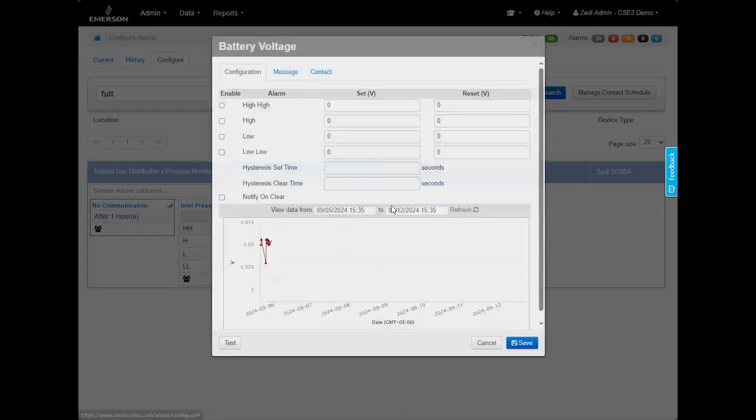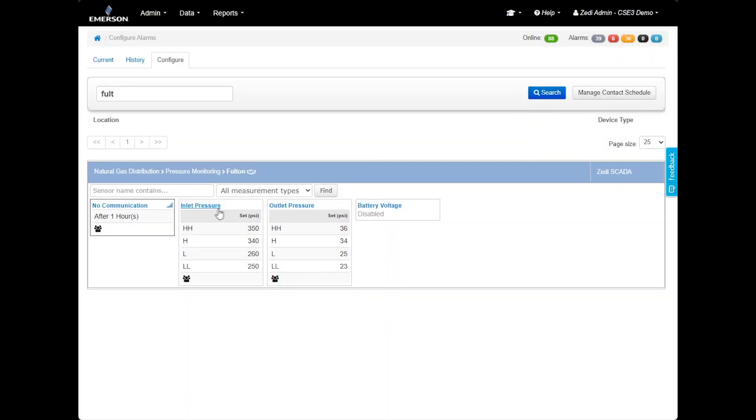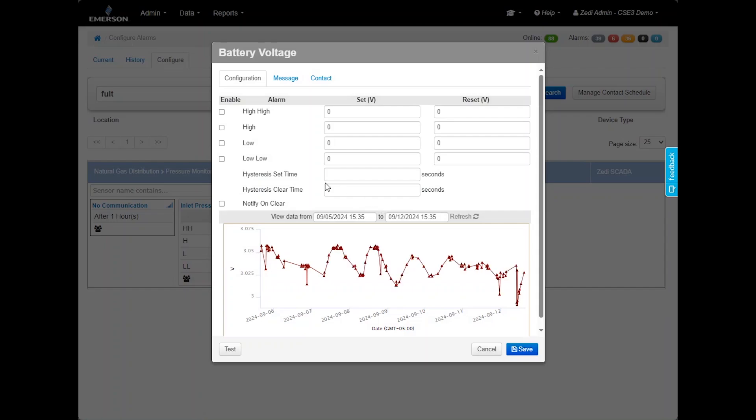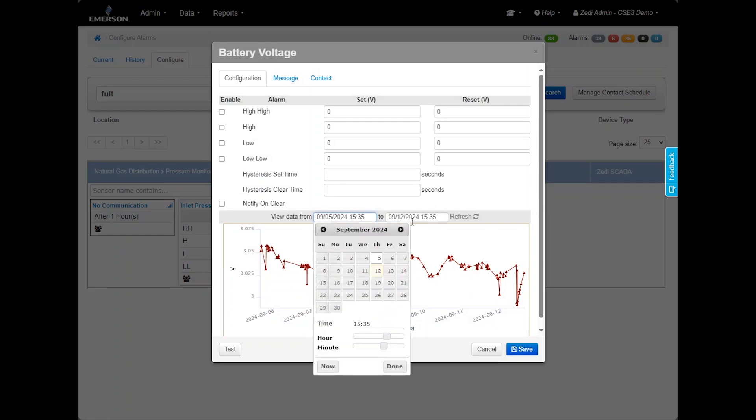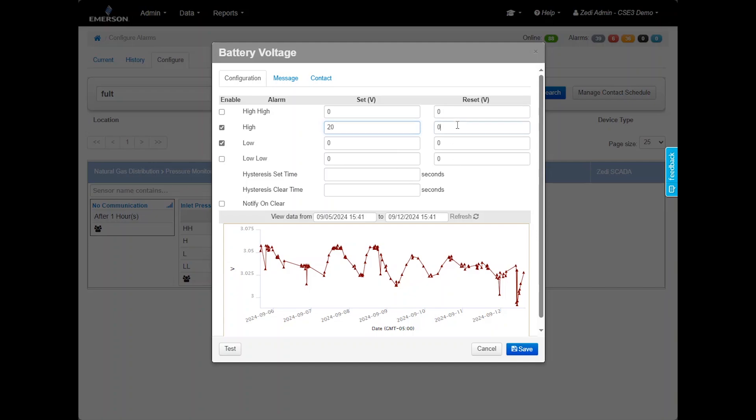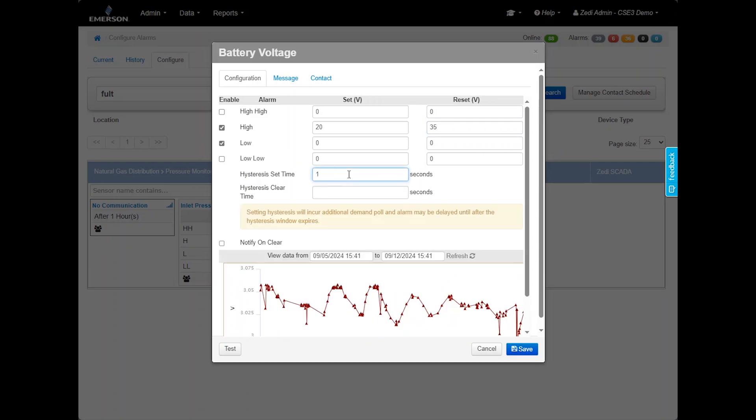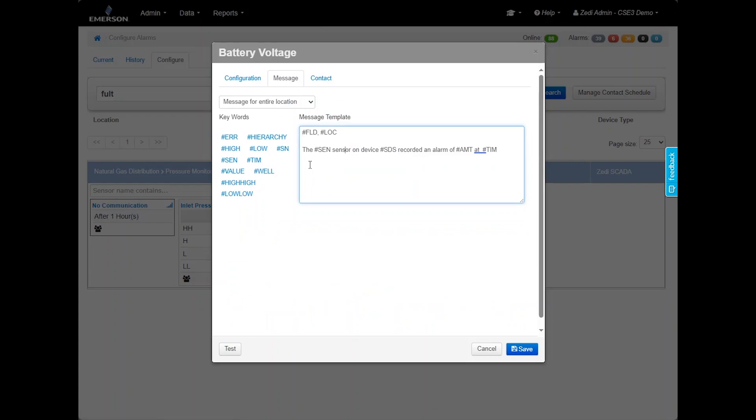Next, select other sensors to configure their alarm settings. These are sensors that are already set up for this site. If you need to configure an alarm for a sensor not listed on this page, please contact Zedi SaaS SCADA for assistance. For this example, let's use the battery voltage alarm. On this page, you will see the 7-day trend graph that you can adjust by setting the desired date and time range. To configure the alarm, check or uncheck the boxes to enable and disable the alarm. Enter the values for triggering and clearing the alarm. The set value determines the threshold at which the alarm is triggered, while the reset value defines the threshold at which the alarm is cleared. The hysteresis set time feature delays both sending and clearing an alarm by a predetermined period. This helps prevent users from receiving frequent, individual alarms for temporary fluctuations. The system performs an additional demand poll to confirm that the device remains in alarm state before it sends out a notification. This ensures that only sustained alarms will trigger notifications, reducing the likelihood of being overwhelmed by transient or minor issues.